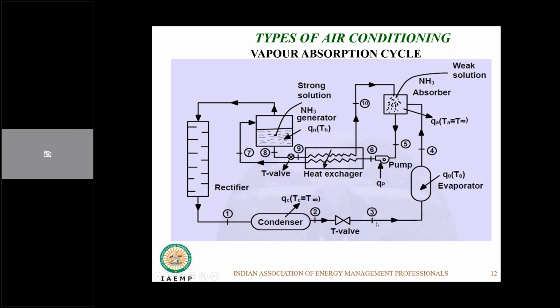Again, the philosophy remains the same. Through the expansion valve, when it comes out, part of the evaporated liquid cools the liquid further down, and as it comes into the evaporator, it absorbs the heat either from cooling water, if it's a chiller-based system, or a DX or an air-based system. It will absorb the heat from the air or a chiller, and it will form the vapor.